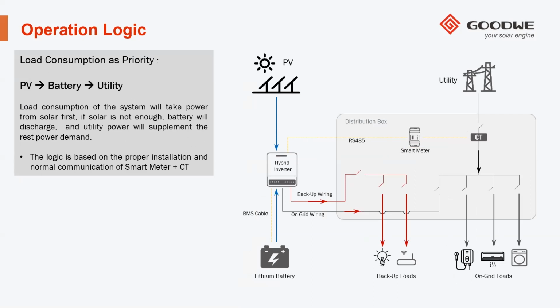Load consumption of the system will take power from the solar first. If solar is not enough, then it will use the battery power. And then lastly, it will use utility power. So if you design a system and your loads exceed the PV production, you'll never really charge your battery. So then it's best to select a mode that will keep your battery full for outages.